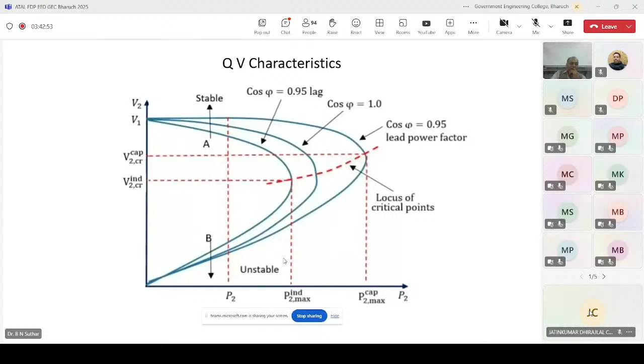At the same time, if your power factor is low, like 0.95 lagging, you can see these two voltage values. There is a difference in the voltage magnitude. So your voltage will tell you that you are increasing the load and your voltage is going down, so it will create a problem. But if your power factor is a very good leading power factor, then you will reach the critical point, and then you will understand that the voltage is going down and now I will have some problem of voltage stability.